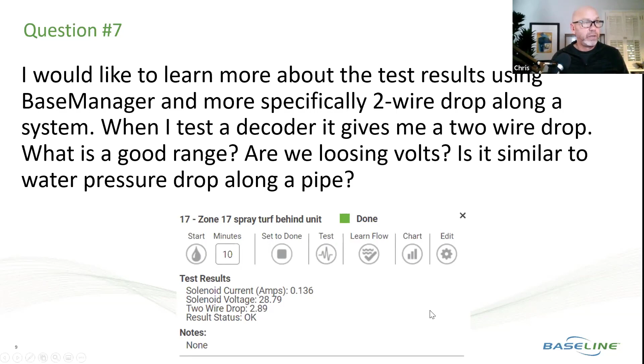Yeah. So like you said, Dan, health of the wire path over time can degrade. You can lose your wire path health over time. So if you, let's say, installed the site and you wrote down your 2-wire drop, maybe that's a good reference point. So a year later, 2 years, 3 years later, what's your voltage drop? I like that. Yep. And we're looking here at a snippet out of quick view of a 2-wire voltage drop of 2.89. I think if you get up around 5.5 or higher, then you're at risk of going into an overcurrent situation, right? Which would require you to find where that voltage loss is bleeding out and creating that short to be corrected so that you resume normal operation.